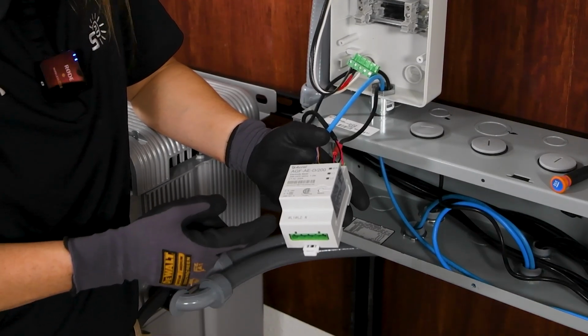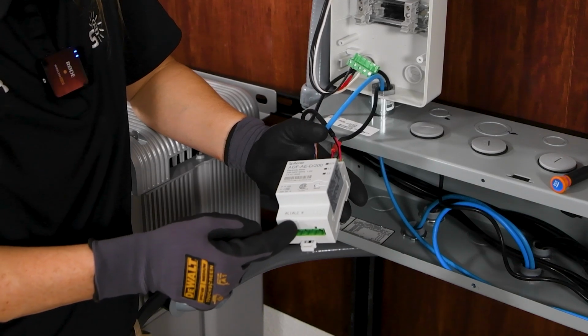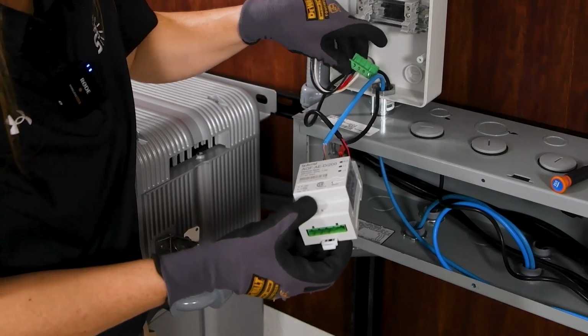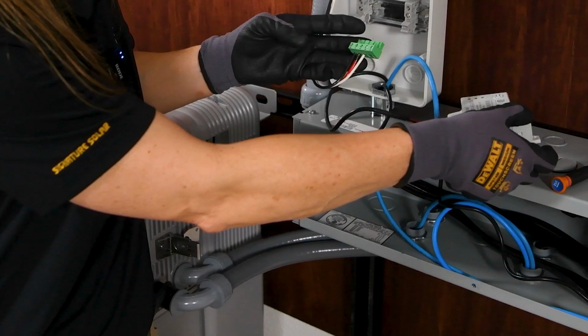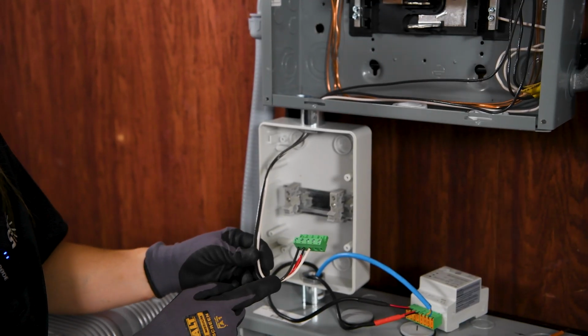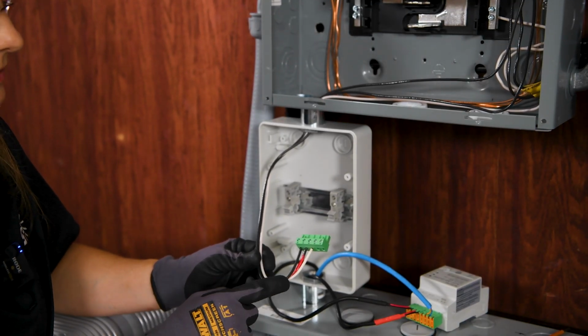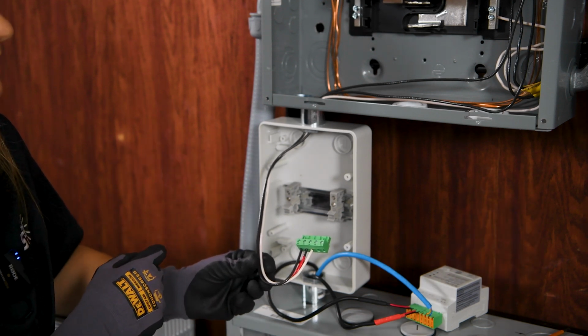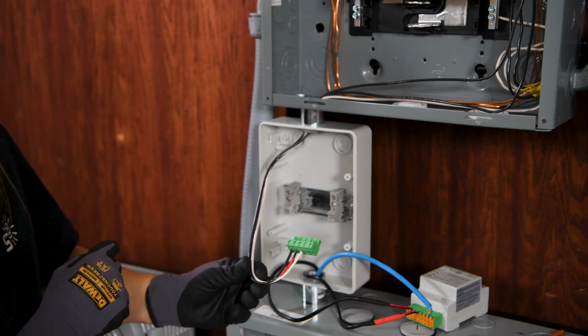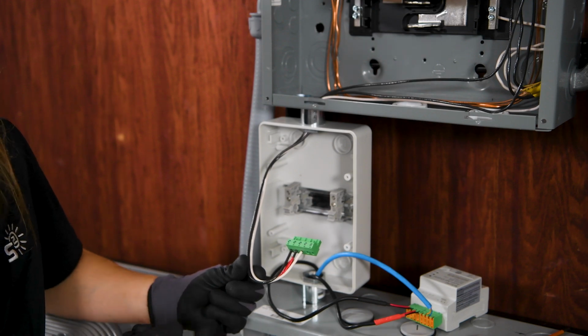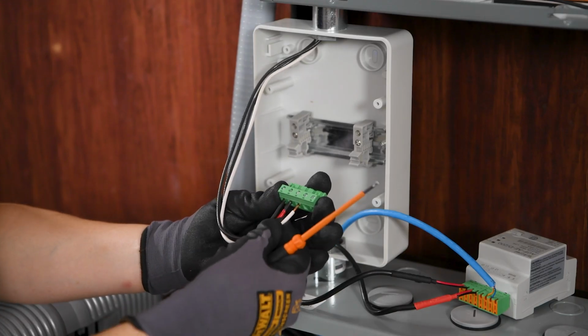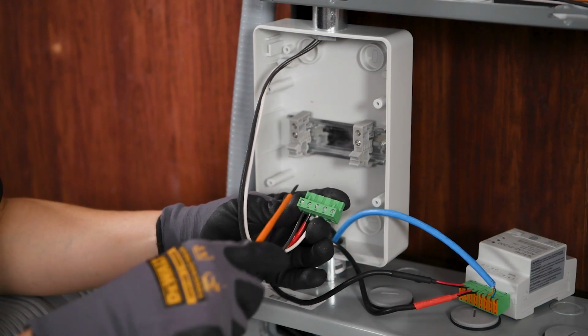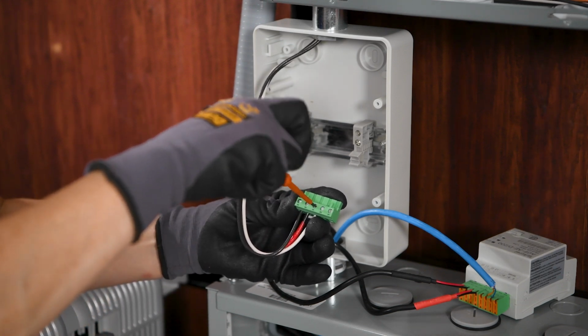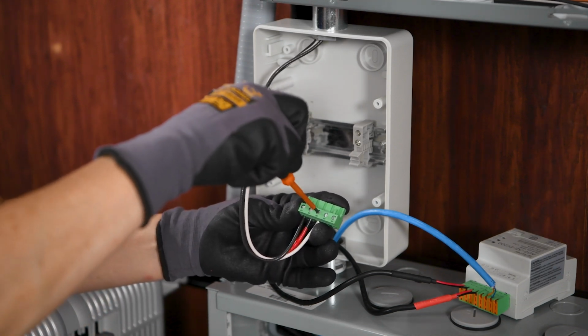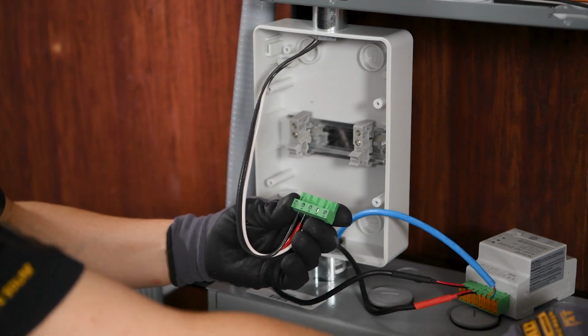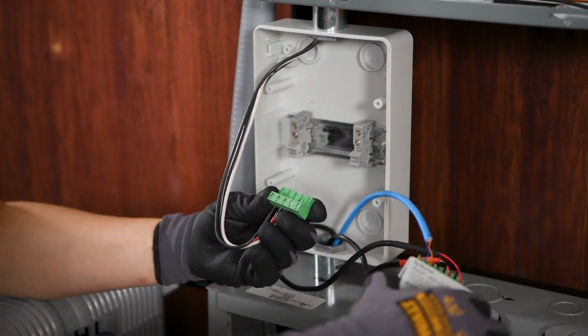The last thing to connect to our meter is our power for our meter, and it's also going to provide voltage reference for us. So we'll connect the L1, the L2, and the neutral, and we'll do that by this 4-pin connector here. Now this is getting power from our backup loads panel, and we're doing this by going to a double pole breaker in our backup panel. We're landing it on actually 2 20-amp breakers. You also need to make sure that you are getting the phases right here, your L1 going to an L1 bus bar and L2 going to an L2 bus bar. This would typically be on your main loads panel coming from your grid.